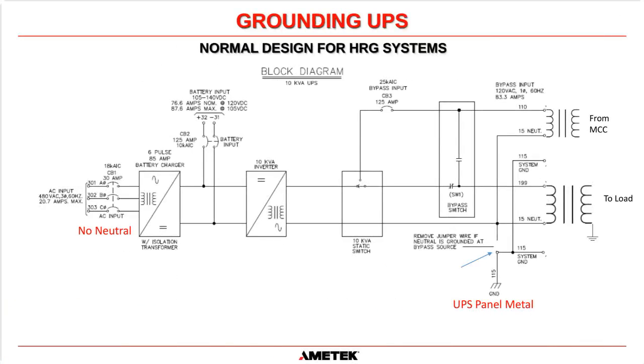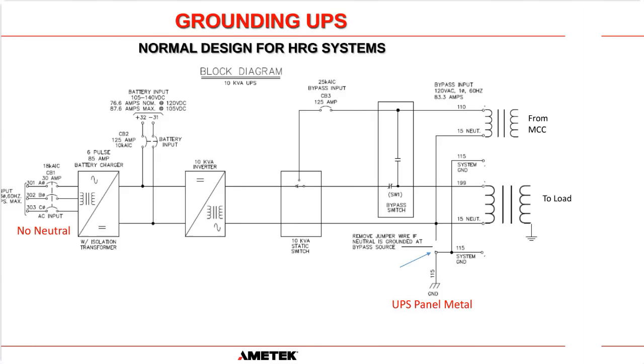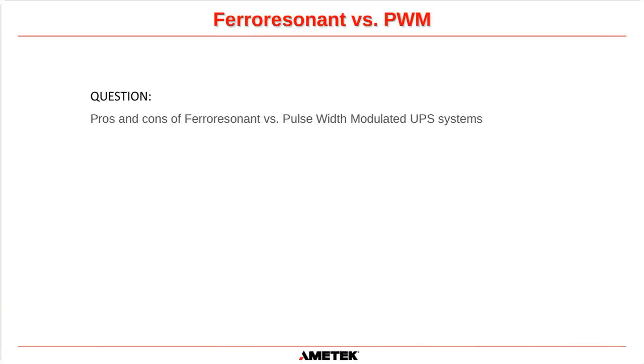So that's high resistance ground circuits. I hope that explained a bit more about where you're supposed to connect the ground circuits on your UPS system. And it's the same for an automatic transfer switch, for an emergency generator, and things like that. Okay.